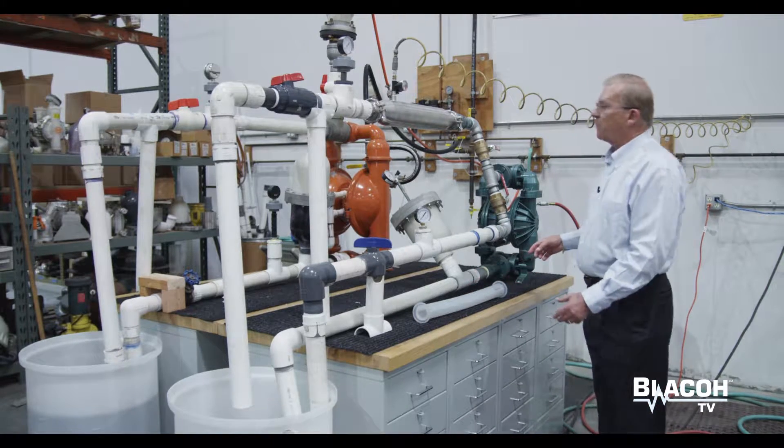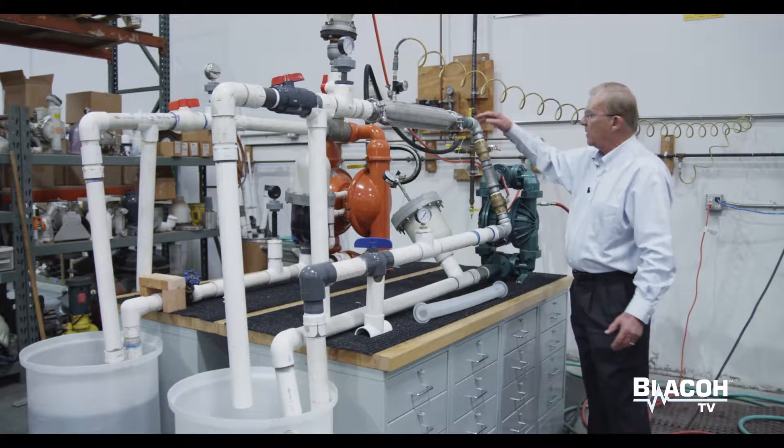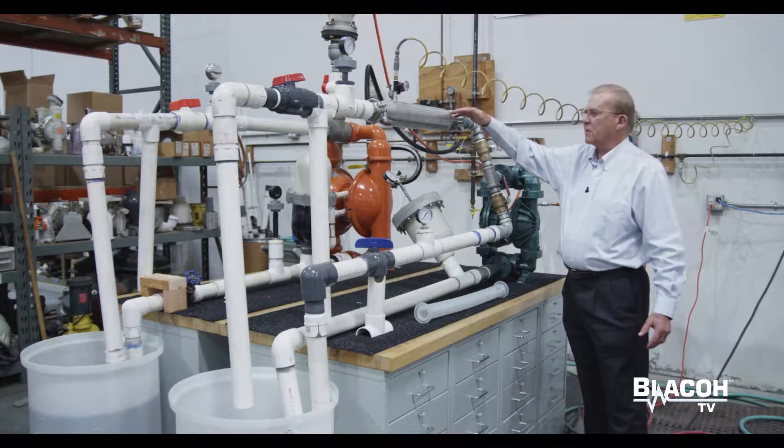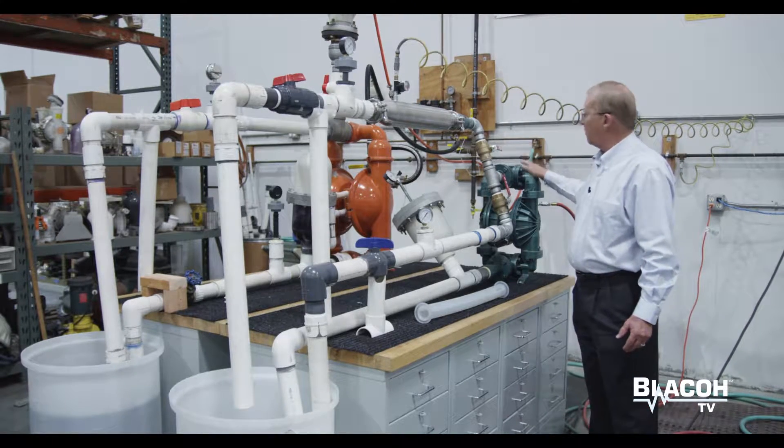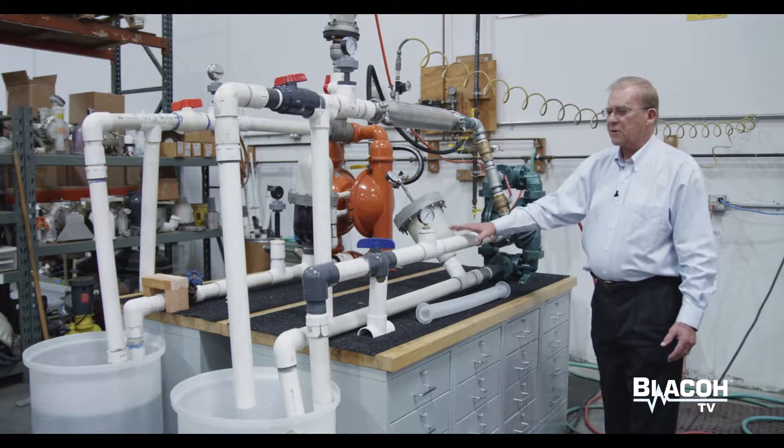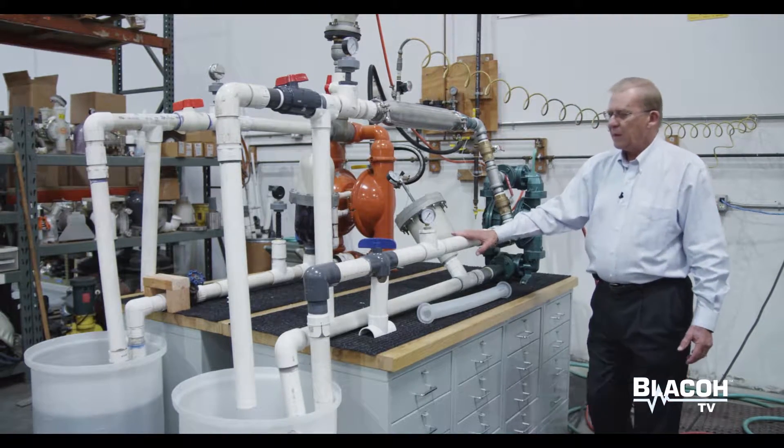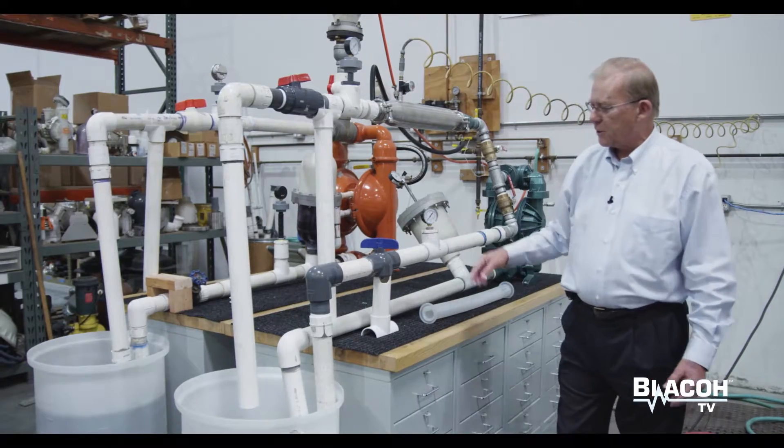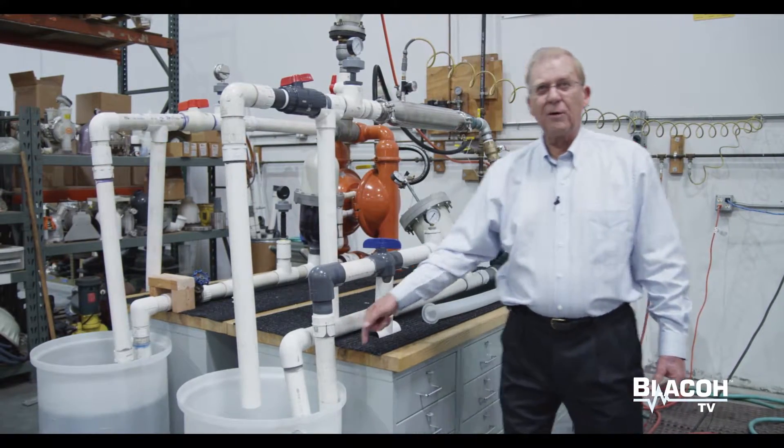So first I'm going to turn the pump on and we have the arrangement set up so that we can pump water from the pump through the dampener or without a dampener. So first we'll pump without a dampener and you'll see the vibration, the pulsation, and the intermittent flow of the liquid.